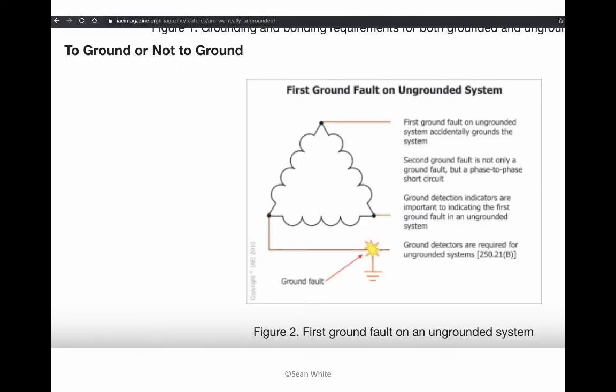Right now what we're doing is we're looking at the IAEI magazine website. And what we can see here is an image of 480 delta. And that's 480 volts, 480 volts, and 480 volts, and it's ungrounded. So none of these are grounded until there's a ground fault. And as it says here in the International Association of Electrical Inspectors magazine, IAEI, the first ground fault on an ungrounded system accidentally grounds the system. So, there you go. It's like you have a grounded system.